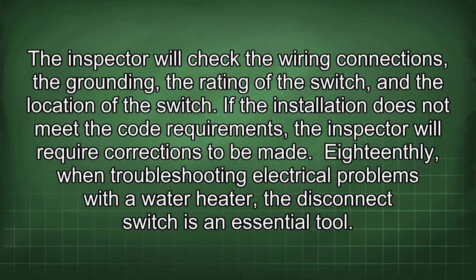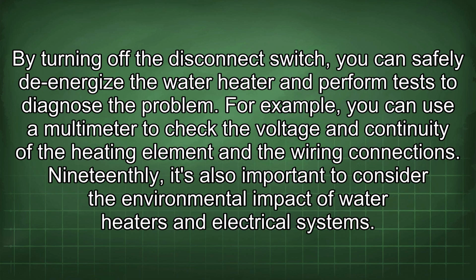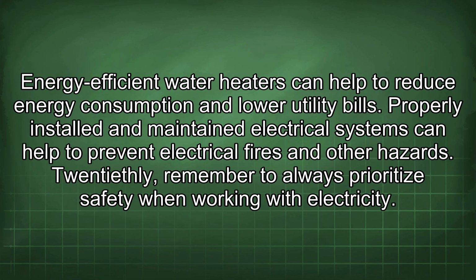18th, when troubleshooting electrical problems with a water heater, the disconnect switch is an essential tool. By turning off the disconnect switch, you can safely de-energize the water heater and perform tests to diagnose the problem. For example, you can use a multimeter to check the voltage and continuity of the heating element and the wiring connections. 19th, it's also important to consider the environmental impact of water heaters and electrical systems. Energy-efficient water heaters can help to reduce energy consumption and lower utility bills. Properly installed and maintained electrical systems can help to prevent electrical fires and other hazards.